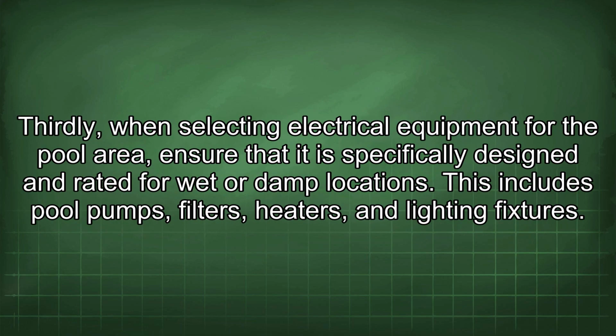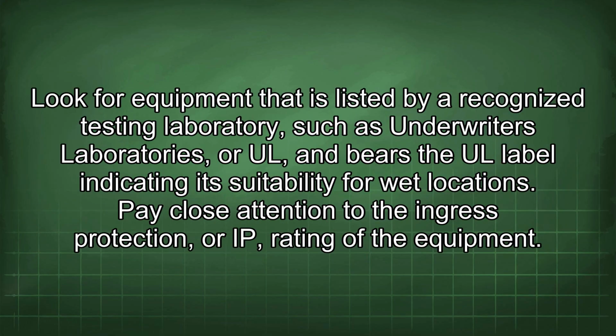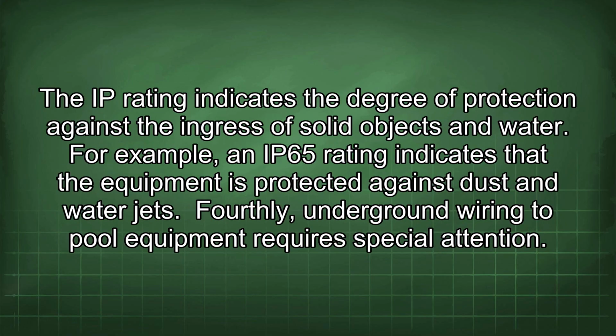of a sink. Thirdly, when selecting electrical equipment for the pool area, ensure that it is specifically designed and rated for wet or damp locations. This includes pool pumps, filters, heaters, and lighting fixtures. Look for equipment that is listed by a recognized testing laboratory such as Underwriters Laboratories, or UL, and bears the UL label indicating its suitability for wet locations. Pay close attention to the ingress protection, or IP, rating of the equipment. The IP rating indicates the degree of protection against the ingress of solid objects and water. For example, an IP65 rating indicates that the equipment is protected against dust and water jets.